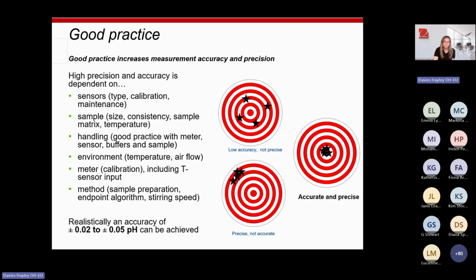The proper handling of the meter, sensor, buffers, and sample in the correct environment. So are you maintaining a constant temperature and you're away from any sort of dramatic airflows? The meter, has it been calibrated? If you're using an external temperature sensor input, has that been calibrated as well? And your methods, so your sample preparation, the endpoint algorithm, your stirring speed, and all of that.